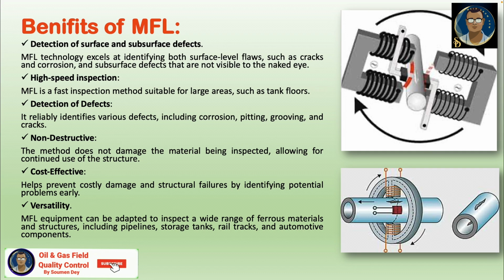Detection of surface and subsurface defect. MFL technology excels at identifying both surface level flaws like cracks and corrosions and subsurface defects that are not visible to the naked eye. So as I told you, this is a magnetic particle inspection. So if you know one of the popular NDT methods used for the welding, that is MPT or MPI, magnetic particle inspection. So it is a similar technology, so you can relate if you compare with this MPI. High speed inspection. MFL is a fast inspection method suitable for large areas such as tank floors.